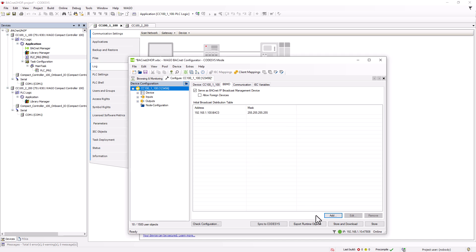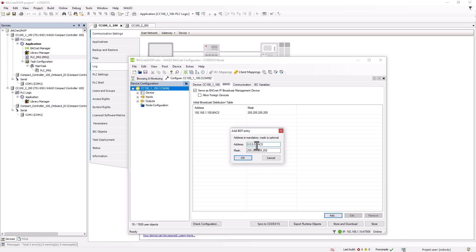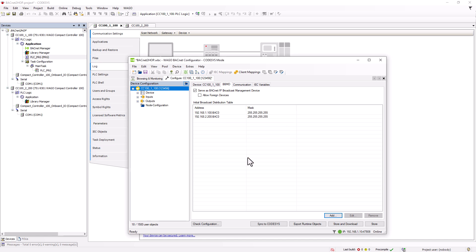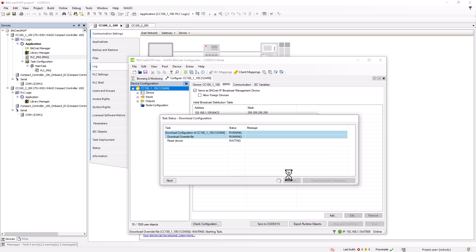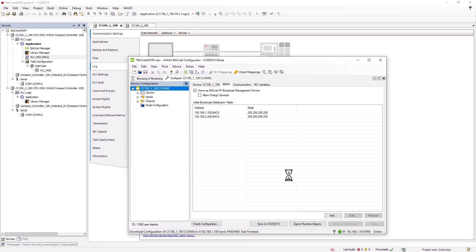Now we need to enter the IP address of the other BBMD in the two network that is our CC100 with the IP address 192.168.2.200. Once the two controllers are in the table, we save them and download them to the controller using the store and download button. Then we synchronize the settings in the BACnet configurator with the CodeSys project.